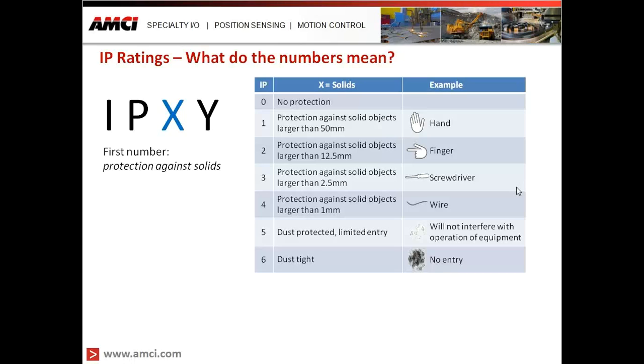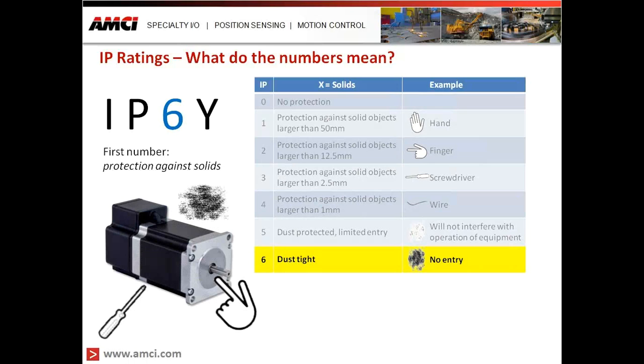Going to a larger number, say four — that item is protected against solids larger than one millimeter. A practical example would be a falling wire: if you're wiring up your cabinet, cut a piece of wire, and it flies somewhere, if it went near an item with a protection level of four, you can be sure that wire didn't fall inside that enclosure. These definitions make it very clear what we're talking about. Numbers five and six provide dust protection — limited entry at five, meaning any dust that does get inside will have no interference with operation, all the way to IP six, which is fully dust-tight.